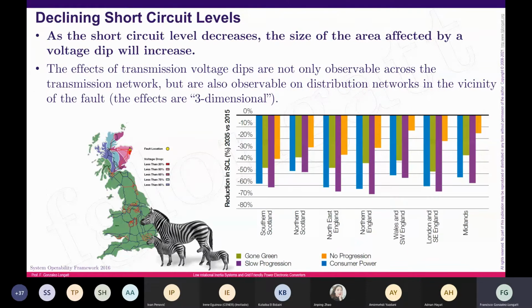If you are not familiar with the GB system, it is already having this kind of issue. There are a couple of documents from 2016 where we have serious concern about the short circuit level for 2035. The short circuit level has started to decrease, and the main source of this decrease is coming from the integration of many interconnectors using HVDC, but also a lot of power plants using power converters like PV systems and offshore wind farms.